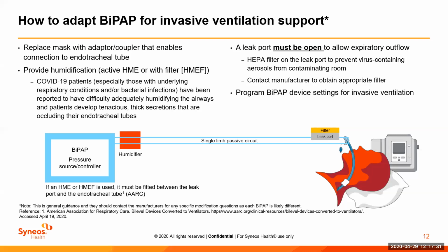In a single limb, however, we put an expiratory filter, an expiratory valve, somewhere near the endotracheal tube or the tracheostomy tube. Then, however you've designed the machine to sense the patient's respiratory status or to breathe for the patient, it'll relax pressure or volume, and then the patient can actively or passively exhale through this little port. There's a number of different types of exhalation ports, whether they be disposable expiratory ports, DEP, which is typical on most single limb circuits, or swivel adapters, which is typical on most home face mask breathing units, or a mushroom valve, exhalation valve. So there's a few different ports that you can use, but this in particular, which we'll be reviewing, is the disposable expiratory port.